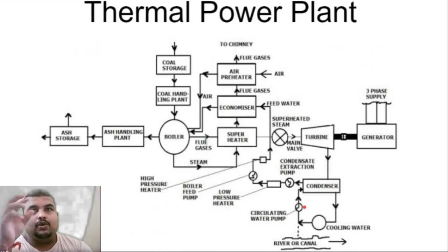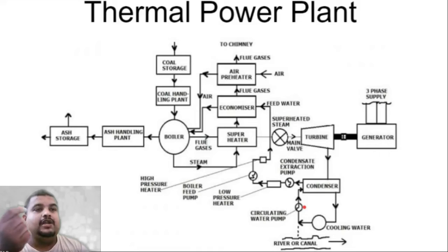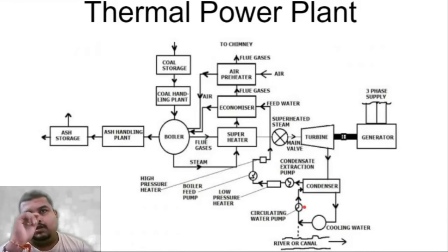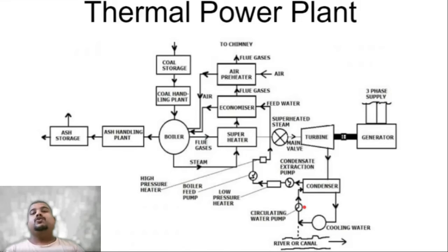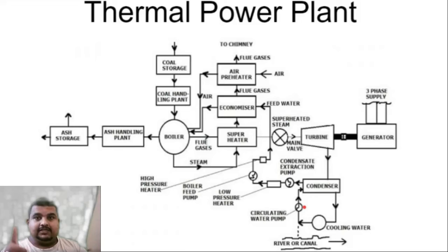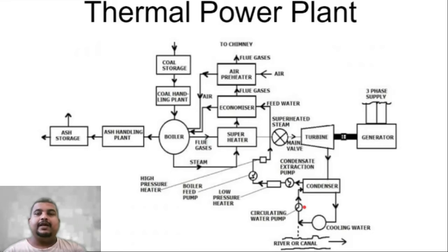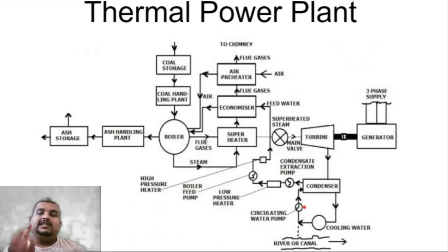The coal bunkers provide coal to the coal mill, which crushes and converts the coal into powder form — this is called pulverizing. Why is coal pulverized? So that the surface area of the coal increases, which makes burning easier and increases the efficiency of the burning process. If burning is incomplete, coal is wasted — for example, if you spend 100 rupees on coal, only 50 rupees worth actually burns. By increasing the surface area, we improve combustion efficiency.